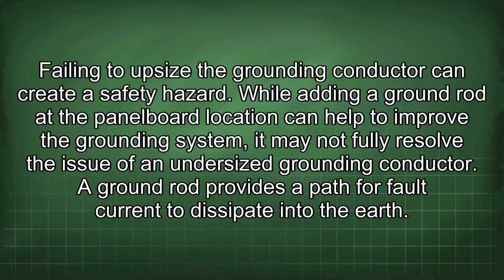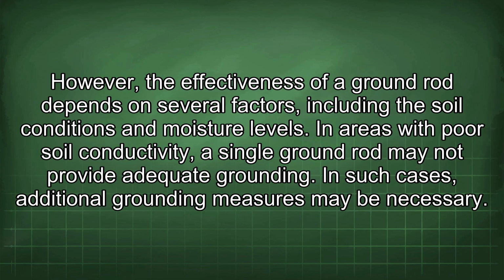While adding a ground rod at the panel board location can help to improve the grounding system, it may not fully resolve the issue of an undersized grounding conductor. A ground rod provides a path for fault current to dissipate into the earth. However, the effectiveness of a ground rod depends on several factors, including the soil conditions and moisture levels. In areas with poor soil conductivity, a single ground rod may not provide adequate grounding.